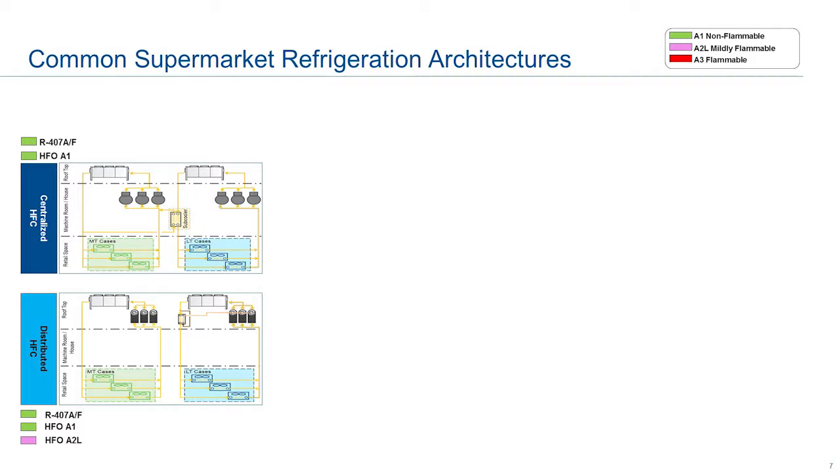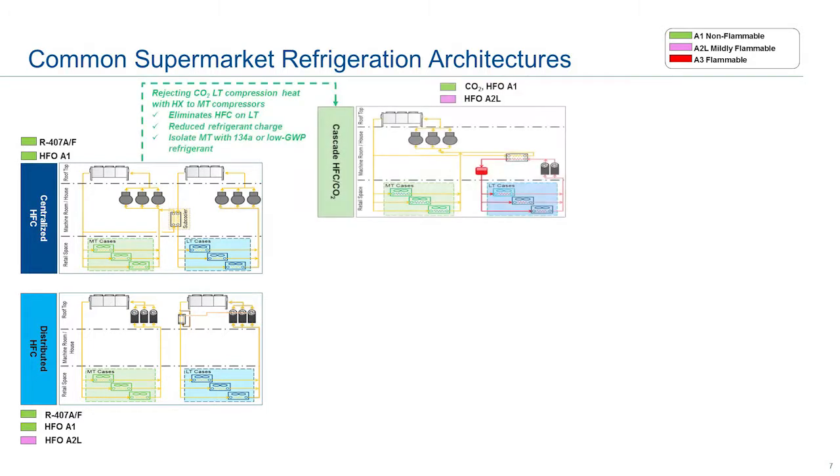Currently two prevalent architectures are being employed in our food retail space: the centralized refrigeration rack architecture and the distributed rack architecture. Both architectures use HFCs. There are multiple permutations, one of which is a cascade architecture that has the ability to eliminate HFC on your low temp, allowing you to use CO2 on the low temp. In doing that, you're adding heat exchangers, reducing your refrigerant charge, and you have an architecture that eliminates a little bit of HFC.